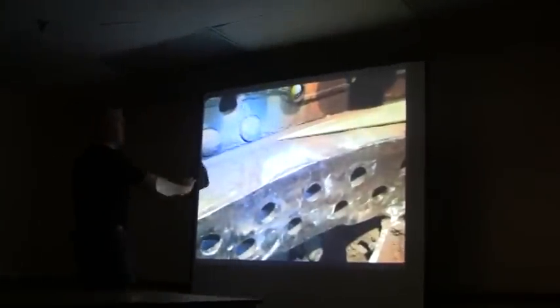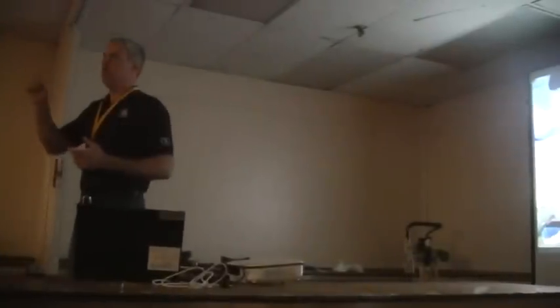So we very carefully ground that out, and fortunately that grooving did not extend below that length. This is a big piece of steel known as the mud ring. And this outer sheet is riveted to the other side here. The rivets move through here. So fortunately, that grooving was only present from this level up. And that's not the worst of it, unfortunately. There was some more that was a little bit worse. But as you measure it from the outside with an ultrasonic test probe, you can get an idea of what the thickness of that plate is. Here's a close-up of the grooving.